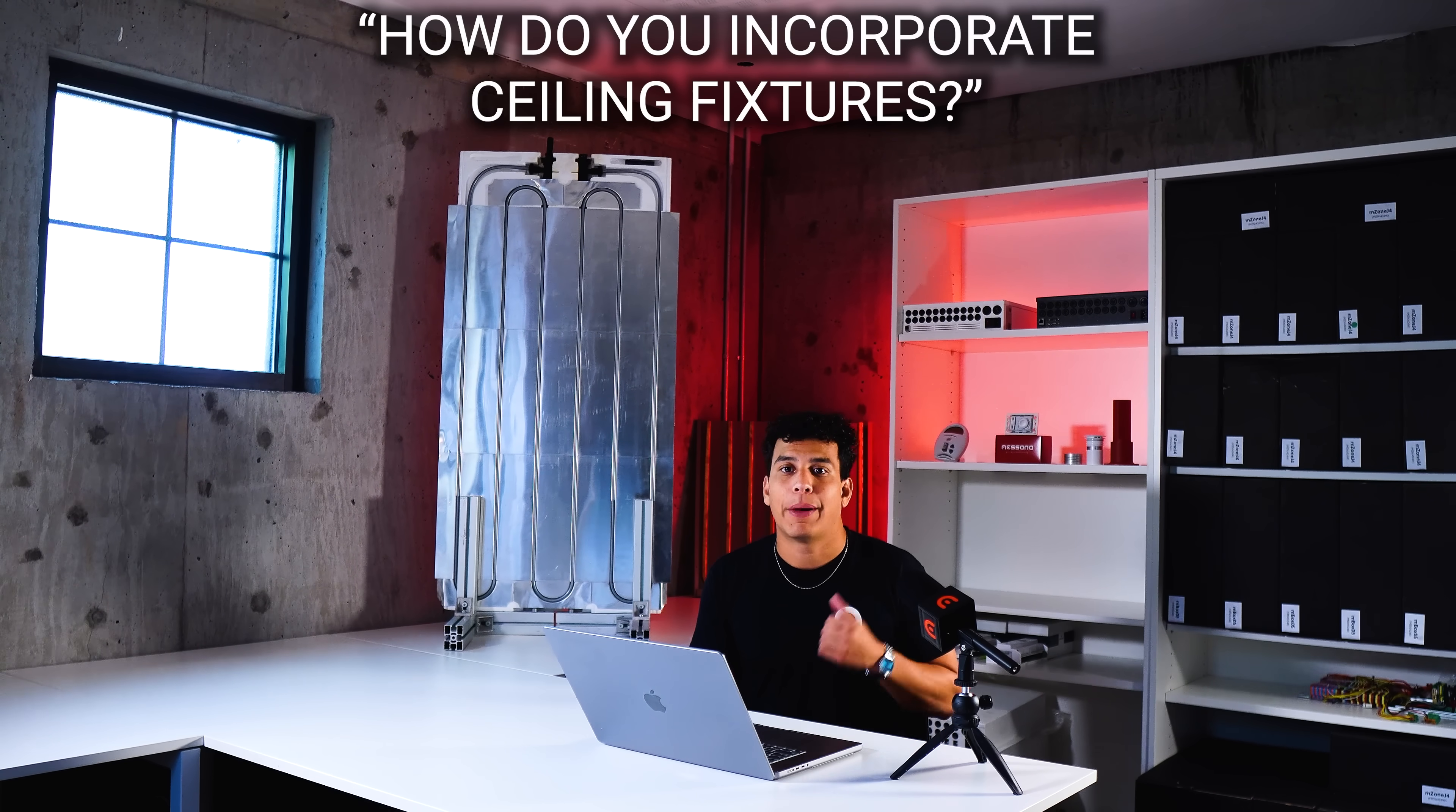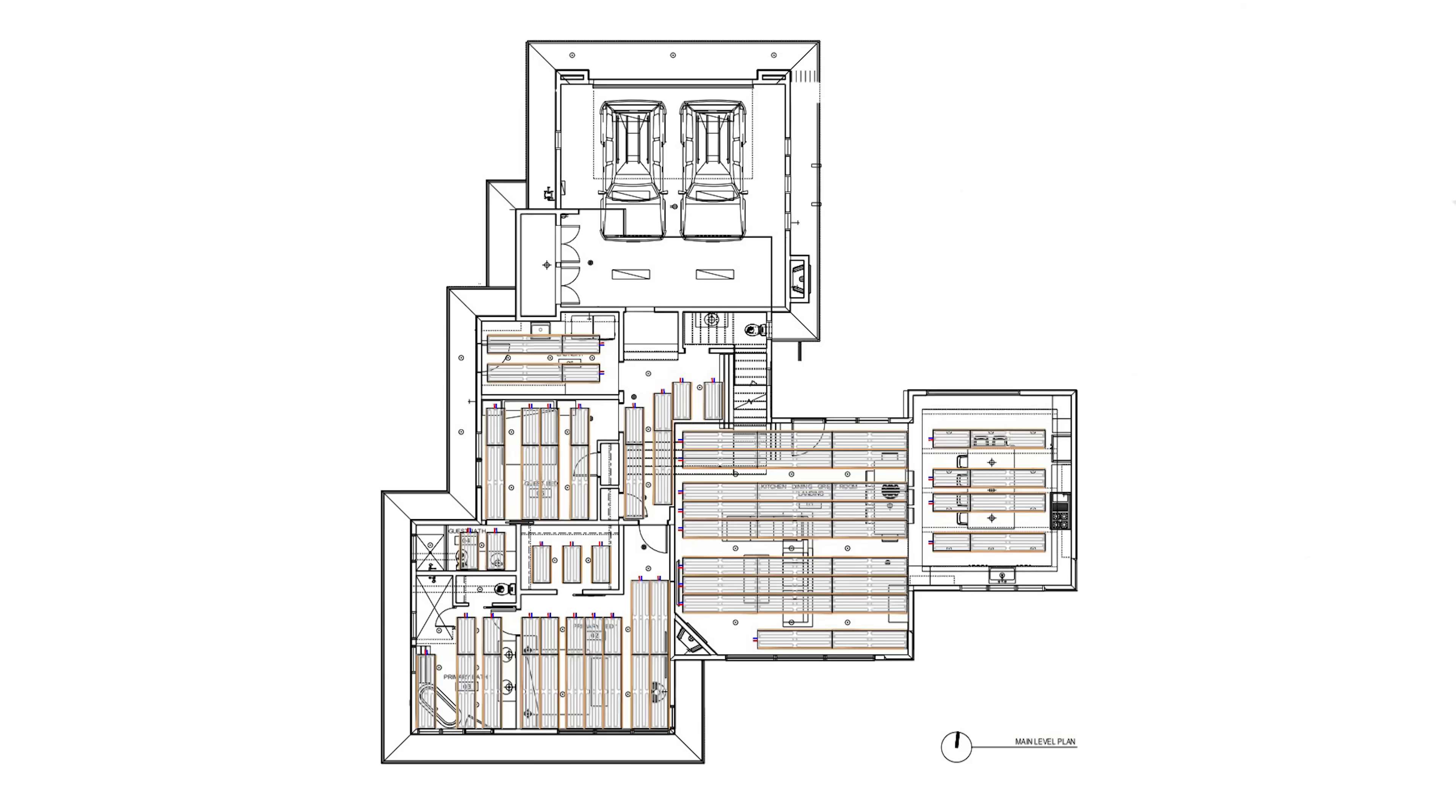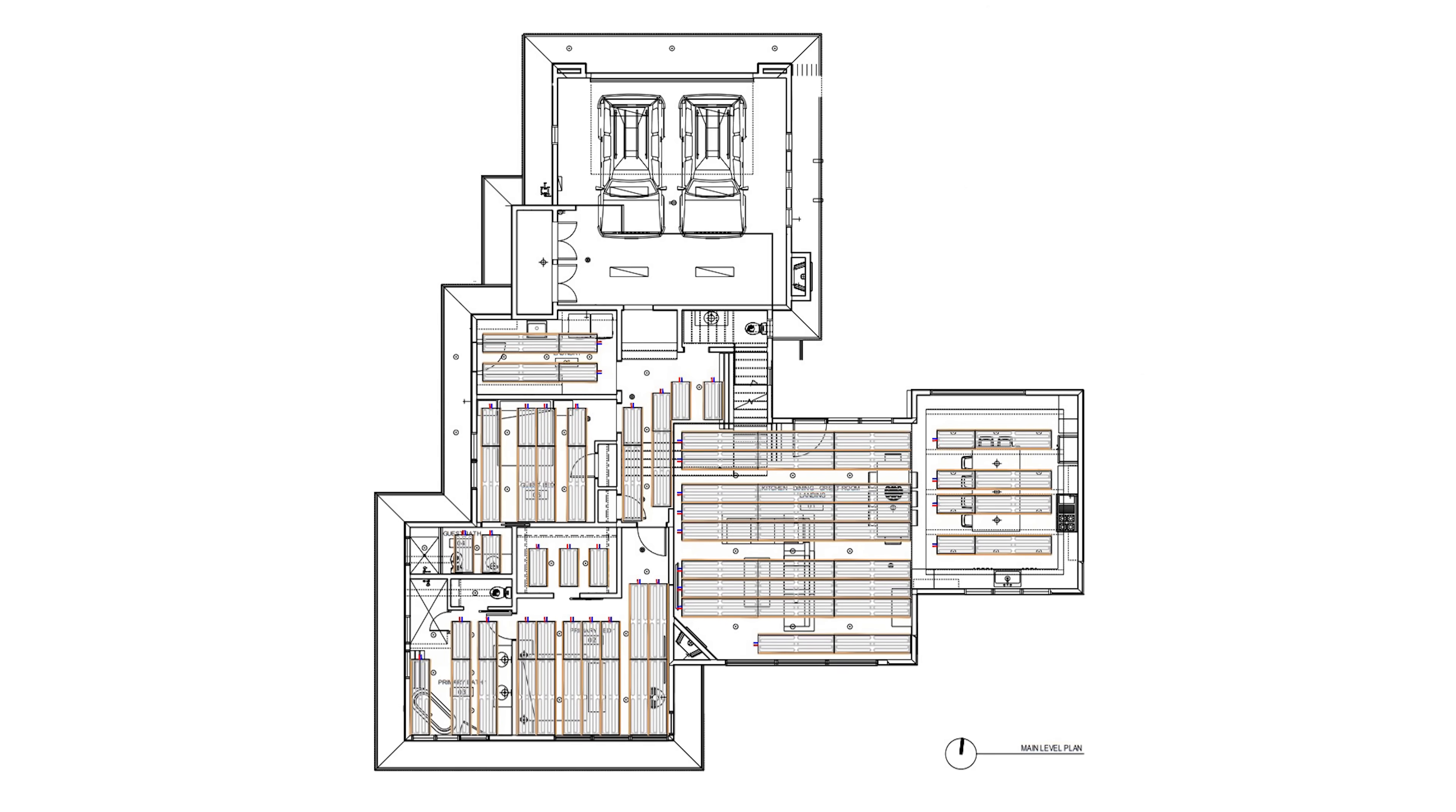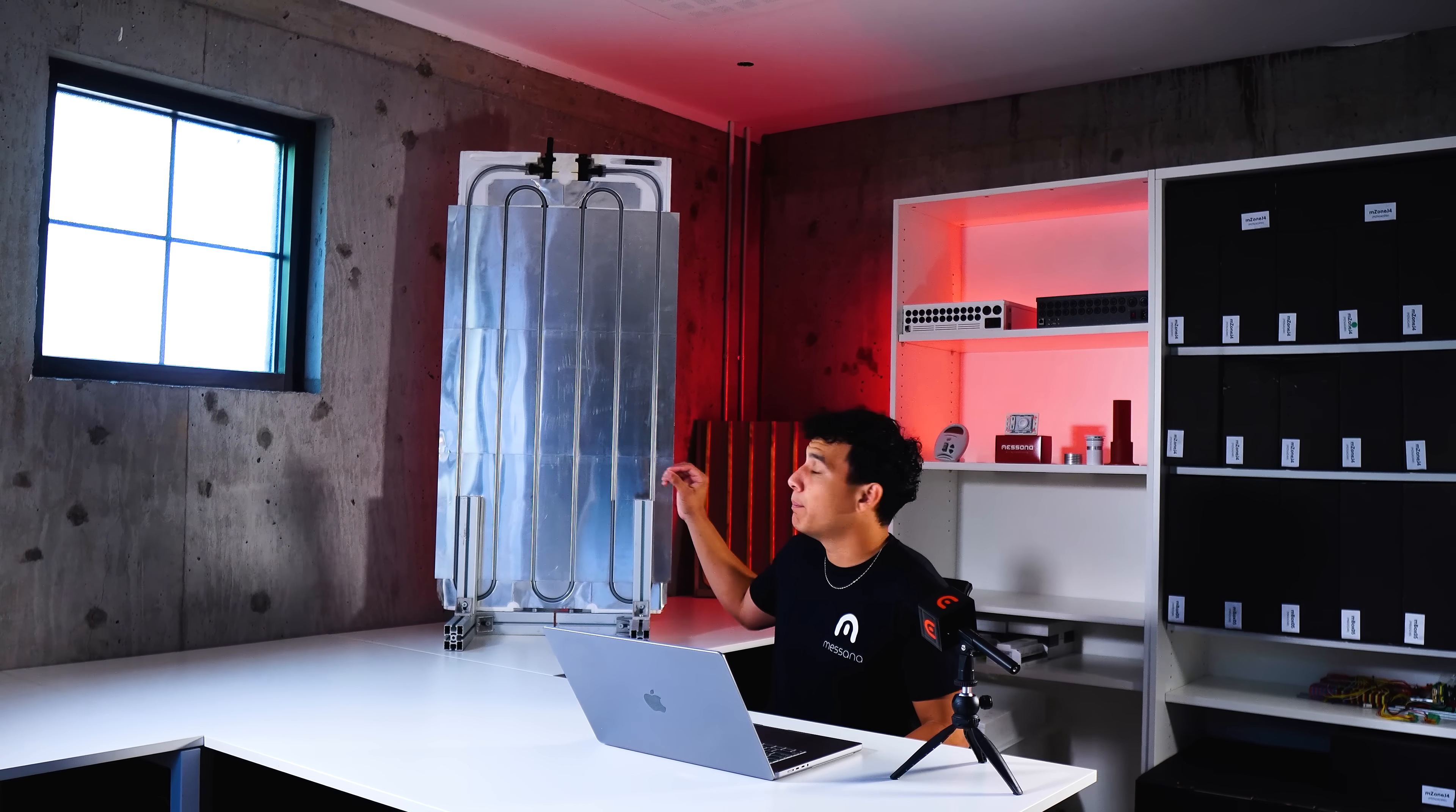Question number three has to do with ceiling fixtures. People often ask about lights, sprinklers, speakers, stuff that would go in your ceiling, and how we would work around that for a radiant ceiling system. During the design phase, we do try to work around ceiling fixtures like lights and sprinklers. We do that in the panel layout to avoid them. But if we cannot reach our desired radiant surface area when we've avoided these ceiling fixtures, we can actually put holes in the panels in various spots and sizes.